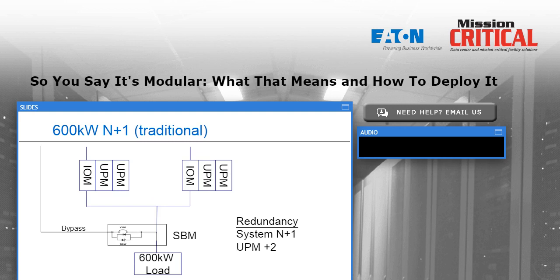This, again, is showing a 600 kilowatt UPS with the N+1 capability, and the customer is deploying this in a traditional N+1 redundant system. So on the left-hand side of the diagram, you see 2 UPMs and an IOM, which is simply an input-output module where the cabling lands for that UPS. Each UPM is 300 kW, so that's a 600 kilowatt UPS. The critical load, looking at the block in the bottom of the slide there, is 600 kW, but the client desires N+1 redundancy, so they're going to go the conventional route and get another 600 kilowatt UPS system and another set of batteries for that system as well. And then the SBM, or the bypass module, which contains a static switch, if you can see my cursor in this part of the slide here, would be common to both of the separate UPSs.